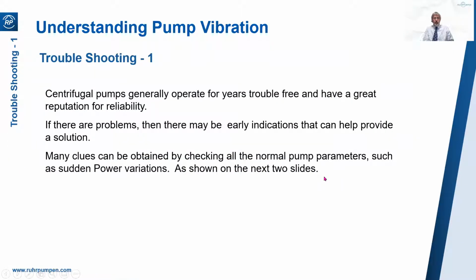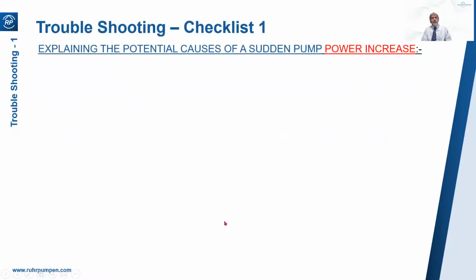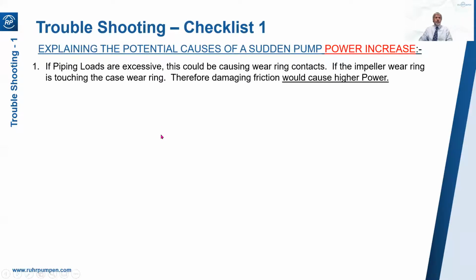Moving on to troubleshooting. So you're getting an elevated vibration reading. The first thing to consider is, is this high vibration reading associated with a sudden power increase or decrease? So first, if it's associated with a sudden power increase, you've got high vibration and a power increase, there are 7 things to look for.